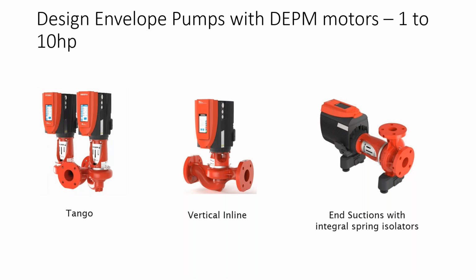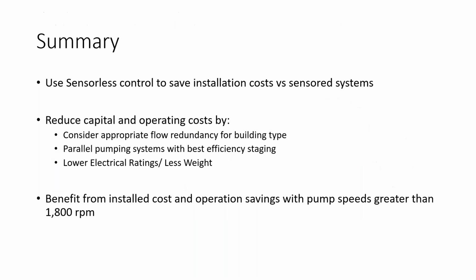And then basically on our design envelope pumps that are currently available, we'll go from 1 to 10 horsepower. So we're covering a nice range, and keep in mind that two 10 horsepower motors replace a single 20 horsepower motor of yesteryear. So the flow range and the capabilities of these units are highly effective. They're available in Tango style, vertical inlines, and end suctions as well. And this is a cute little add-on. It integrates your spring isolators right into the design of the pump. So what an awesome design that Armstrong came up with on that one.